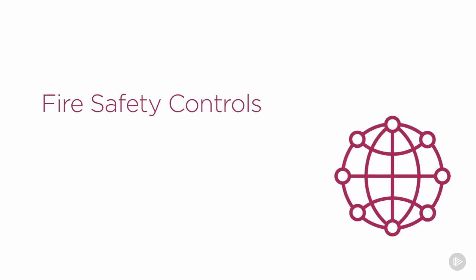So what are some of the fire safety controls? Well, the first step in fire safety is always to prevent it. The second step would be to detect it. And the third, of course, to suppress it or respond to it, put it out. So the best thing is to do regular inspections. Look for the types of conditions that would make a fire more likely. Overloaded, frayed electrical lines, other materials lying around that shouldn't be, and so on. So regular inspections are important, and sometimes even bringing in the fire department can be a good idea. They'll give us advice then on if we have any hazards that we should certainly address.